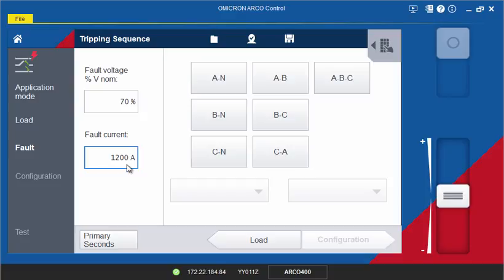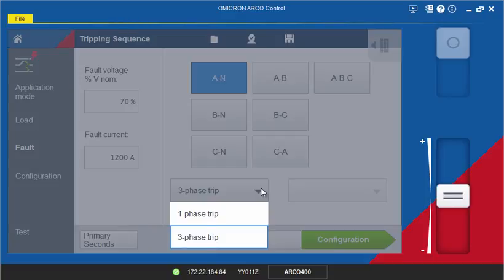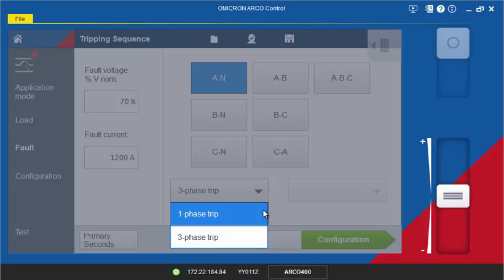On the right-hand side, select the type of fault you want to apply. If you are testing a three-phase recloser with single-phase tripping functionality, select the trip and lockout behavior as set in the controller.